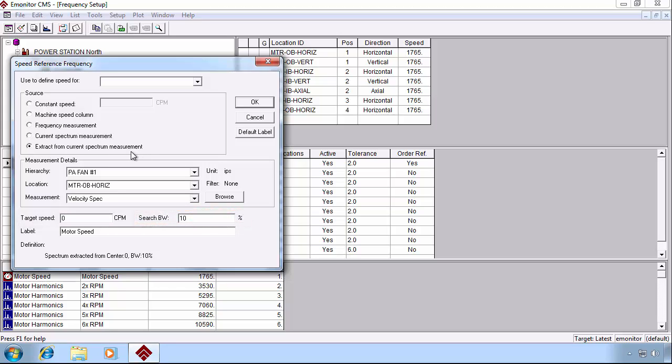E-Monitor will pick the highest peak in that band and assume that is in fact the speed that we're looking for. Obviously, this is only appropriate for machines with a fairly narrow running speed.